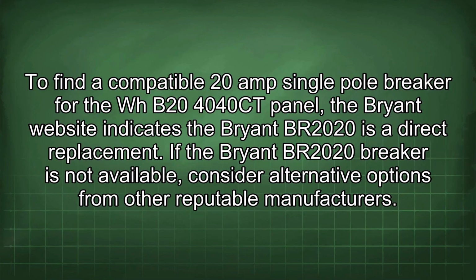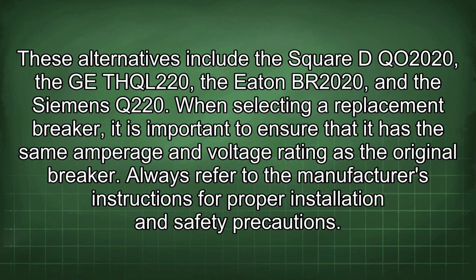Find a compatible 20 amp single pole breaker for the WH B20 4040CT panel. The Bryant website indicates the Bryant BR2020 is a direct replacement. If the Bryant BR2020 breaker is not available, consider alternative options from other reputable manufacturers. These alternatives include the Square D QO 20, the GE THQL220, the Eaton BR2020, and the Siemens Q220.